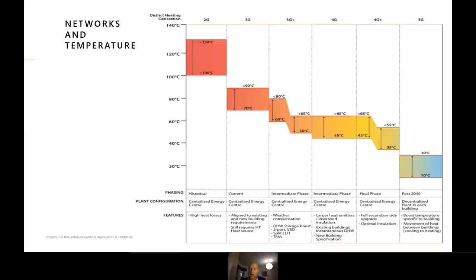And then we have a big jump between that system and a 5th generation system, sometimes referred to as an ambient system or an ultra low temperature network. In that case, you've got very low temperature water, maybe between 10 and 30 degrees, which you're then upgrading for use in the building with decentralized plants. So you have to be a little careful about mixing system architecture between what is primarily a distribution system and something which is an energy sharing network, decentralized, where you're actually doing the active work in the plant room.